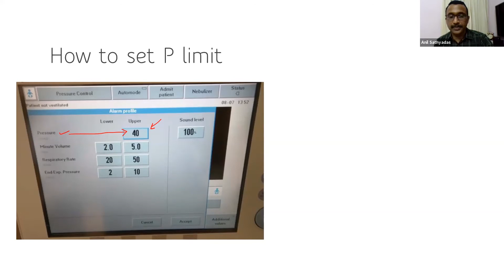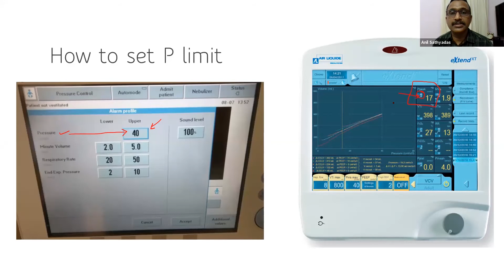It is 40. In other ventilators such as Air Liquide, look in the box that tells you about the P peak. Okay, in that you can have another small box. Again, that is the high pressure alarm. That will again act as the pressure limit. So this is a touch screen. You can touch this small box. You can turn the knob to increase the P limit. But when you increase the P limit, remember you might damage the lung. The lung that is innocent would be damaged, not the diseased lung. Okay.